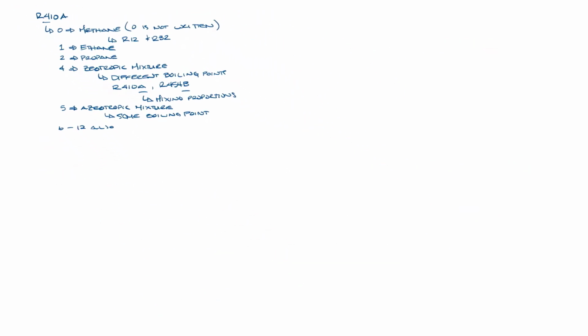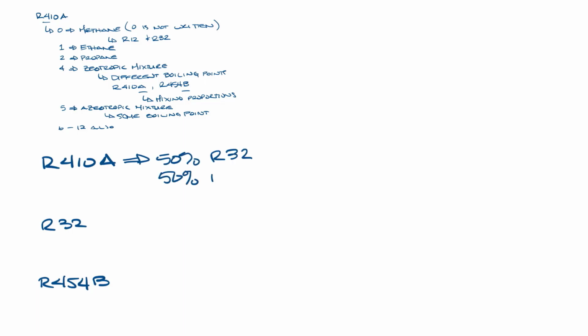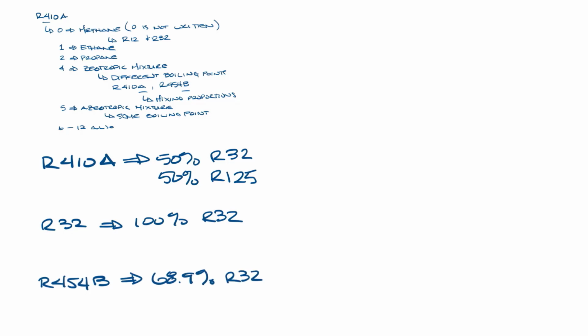So let's move this up here, and let's look at R410A, R32, and R454B. R410A is 50% R32 and 50% R125. R32 is just 100% R32. And R454B is 68.9% R32 and 31.1% R1234YF.